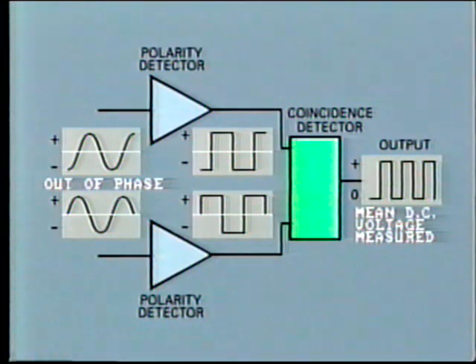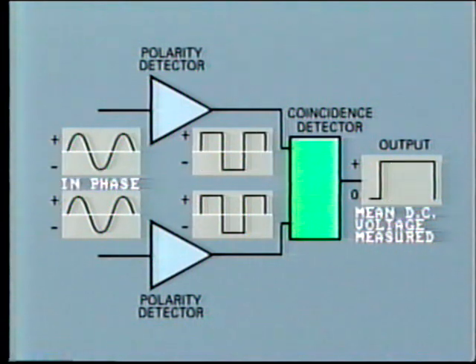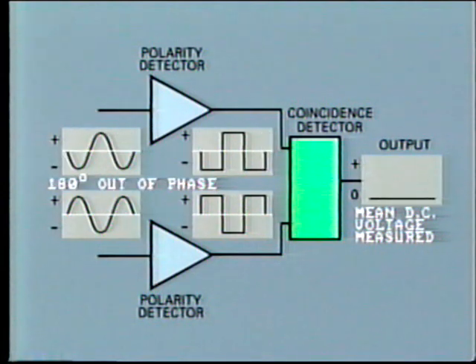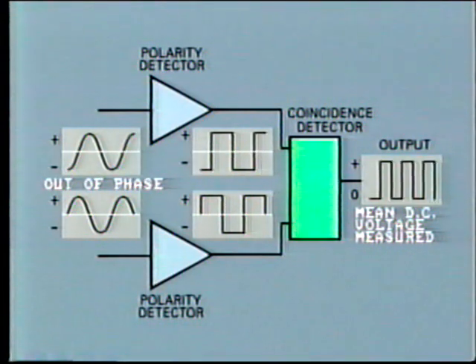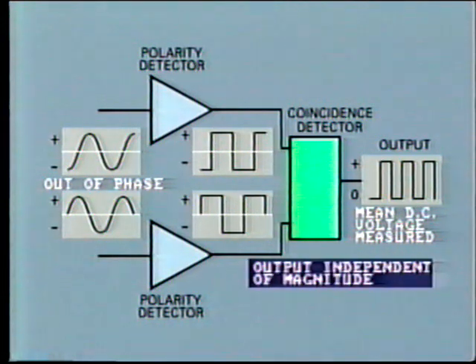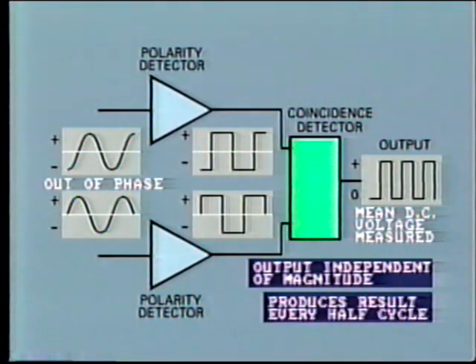The mean DC voltage of these pulses can be measured by integration, usually by charging a capacitor. It will be maximum when the inputs are in phase, and it will be minimum when the pulses are 180 degrees out of phase. This circuit is most useful for measuring phase angle because it is quite independent of magnitude. But it can only produce a result every 180 degrees, that is, every half cycle, 8.3 milliseconds on a 60 hertz system.